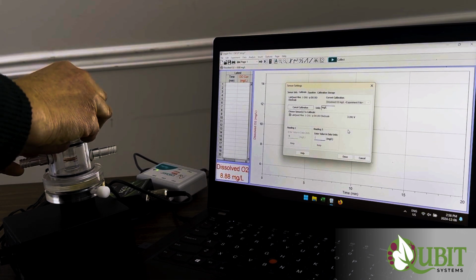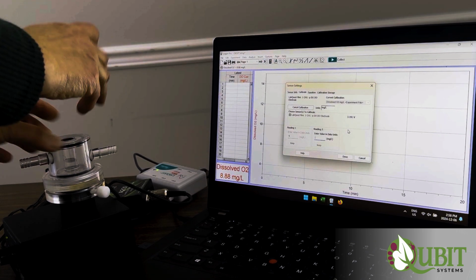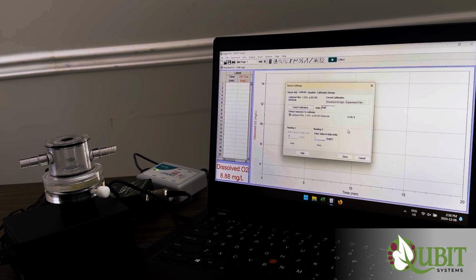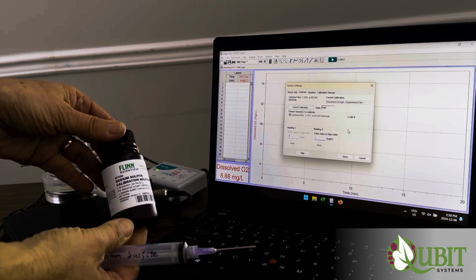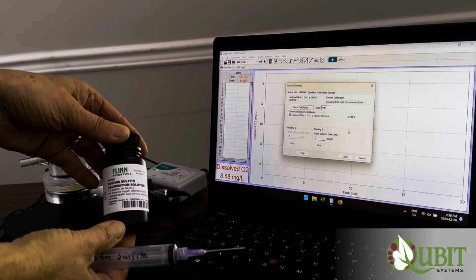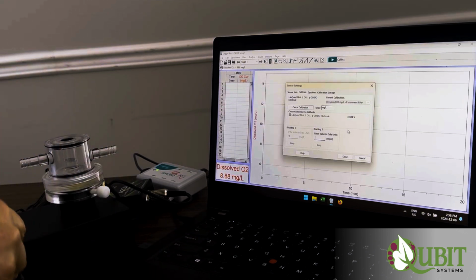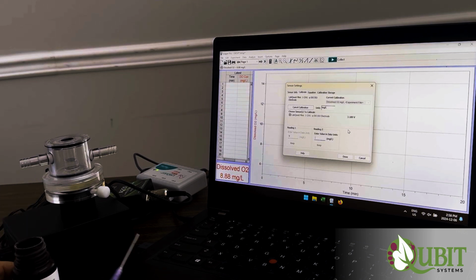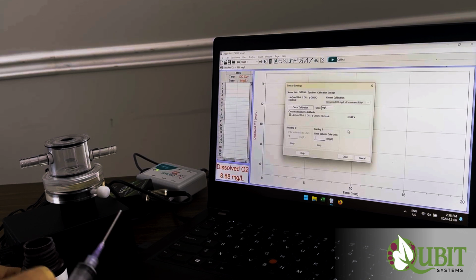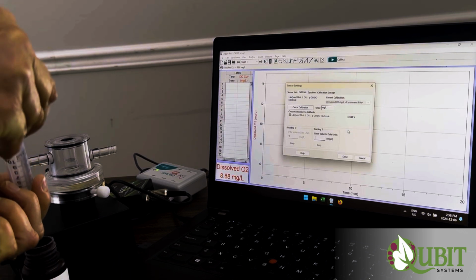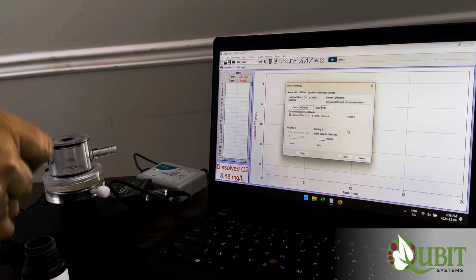For reading 2, we need to obtain a 0 dissolved oxygen measurement. And there are 2 ways you can do that. In your kit, you will find the sodium sulfite solution, which removes any oxygen from water, and we can use that. Another way of doing it is by using nitrogen gas, for example, and bubbling your solution with nitrogen gas. I'm going to use the sulfite.